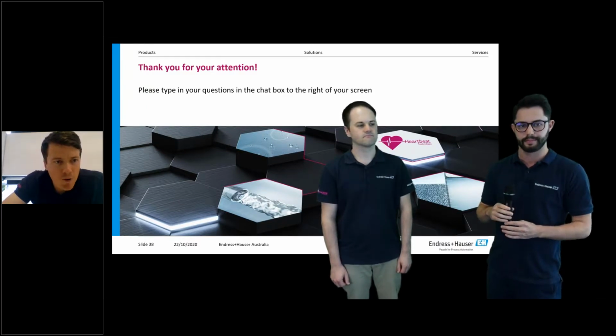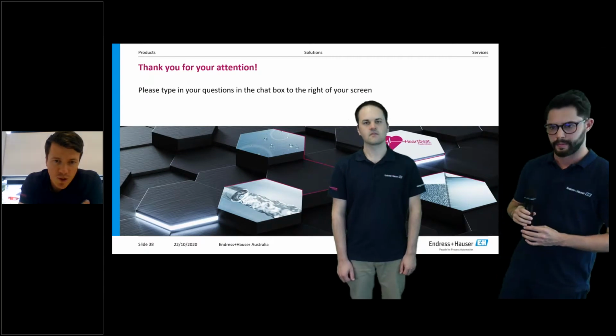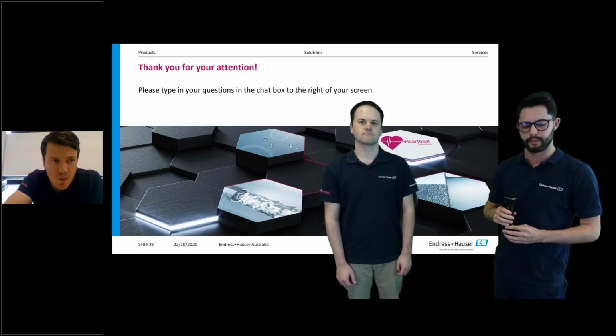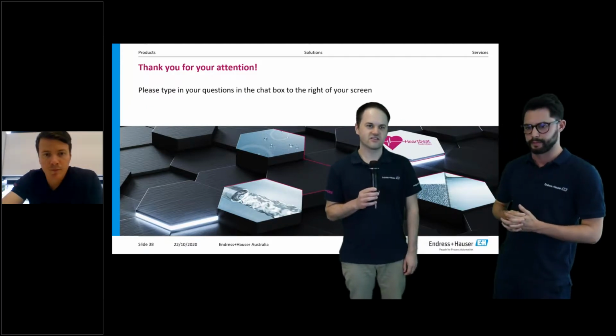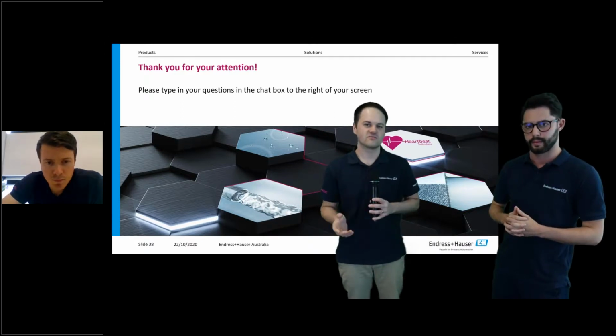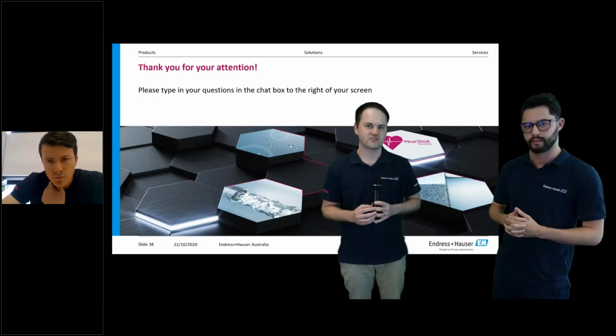Cool. I've got another question here. Someone's mentioned using diagnostics, one of those three pillars, to improve your maintenance procedures. Are there any examples of that, or are you able to talk about that? Yes, this is around how you can use verification to extend your calibration. It depends on what type of systems you have on site, what standards you're following and your maintenance strategy as well. But you can utilize the information gained from the heartbeat verification to determine whether or not you need to calibrate at different intervals.